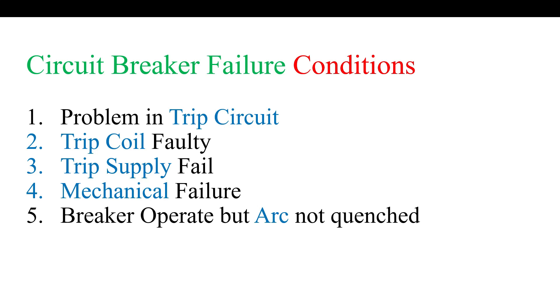The second failure condition is a faulty trip coil. The trip circuit is healthy and the tripping relay is healthy and gives a tripping command to the circuit breaker, but due to the faulty coil the circuit breaker does not operate. In this case the CBF protection will also operate.